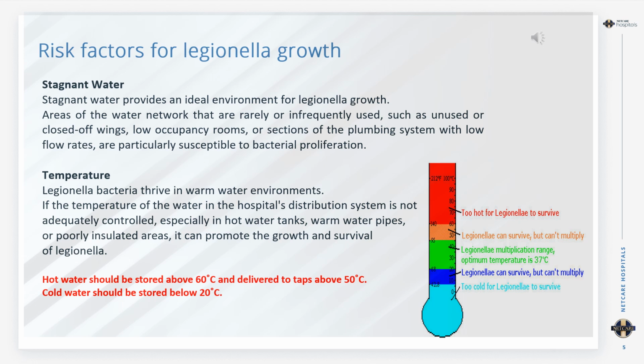So anything between 20 to 50 degrees is definitely not ideal. And between 10 to 20 degrees, Legionella can survive, but it can't multiply. And then anything below 10 in the lighter blue part is too cold for Legionella to survive. So therefore, hot water should be stored above 60 and delivered to taps above 50 degrees, and cold water should be stored below 20 degrees.